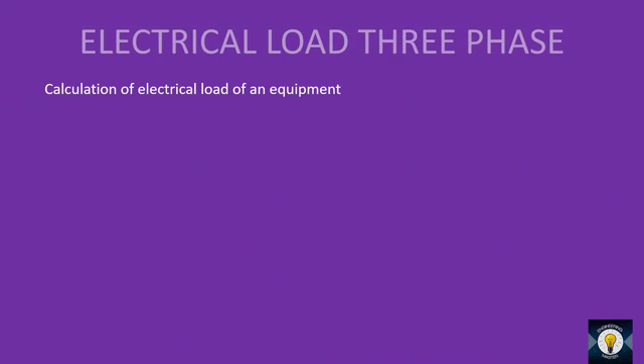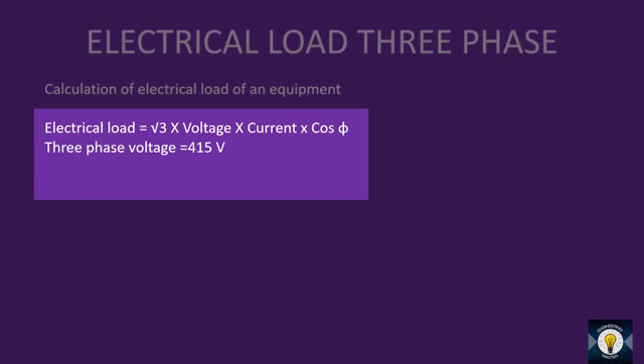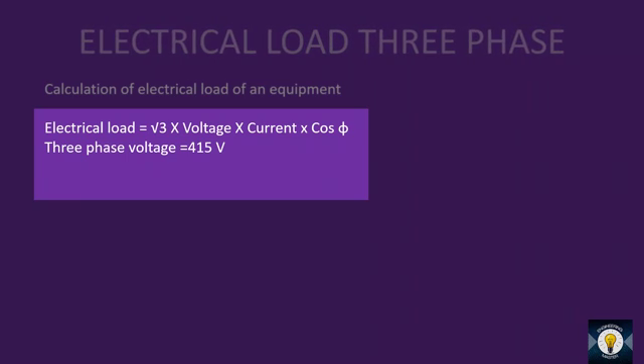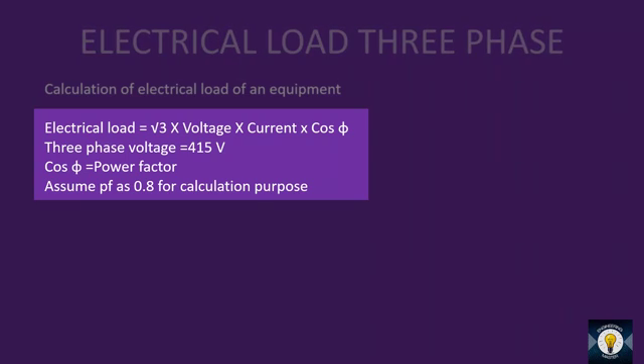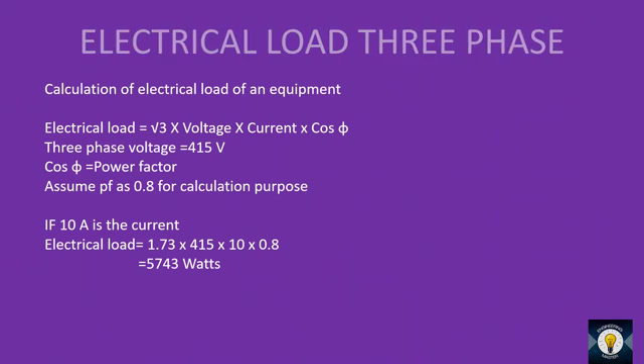In the case of three phase, there is a slight difference: electrical load equals √3 × voltage × current × cosφ. Three phase voltage is 415 volts — I am referring to the Indian three phase voltage; in your country it may vary slightly. Power factor is assumed 0.8. If current is 10A, then electrical load equals √3 (1.73) × 415 × 10 × 0.8 = 5743 watts, or 5.743 kilowatts.